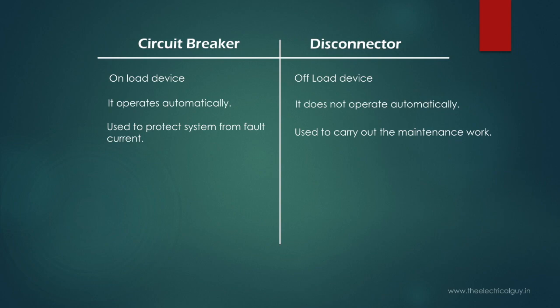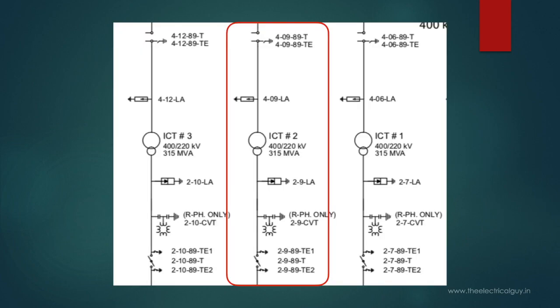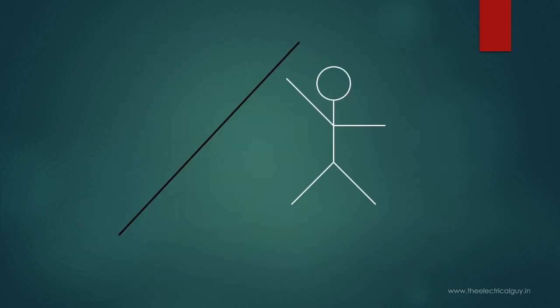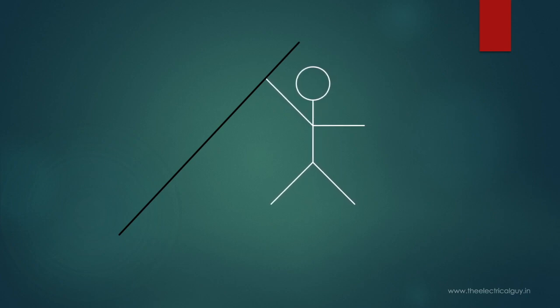Another important application of disconnector is to remove the trapped charges from the system. Consider the same section. To carry out the maintenance we have opened both of these disconnectors. But there is a possibility that there are some trapped charges still remaining in this section.